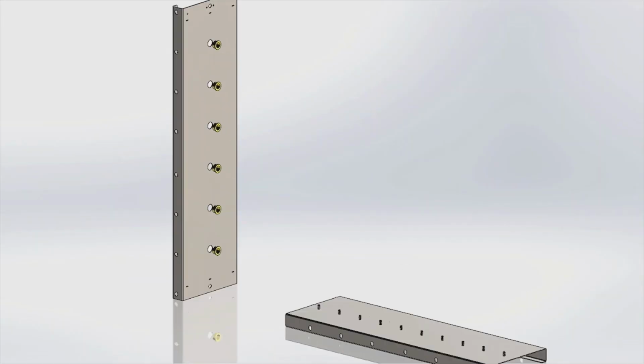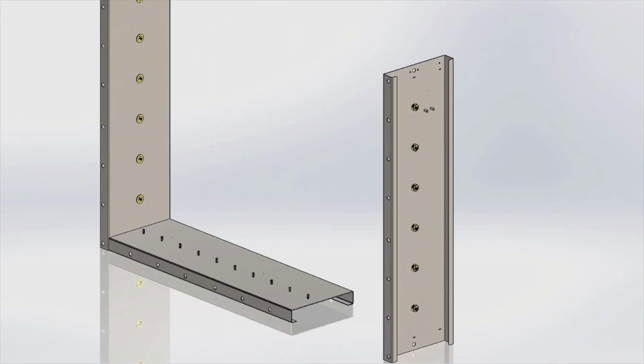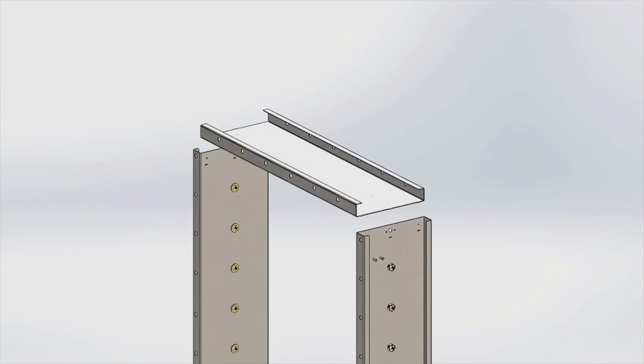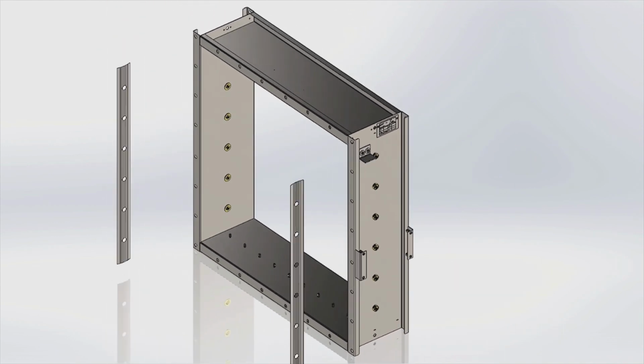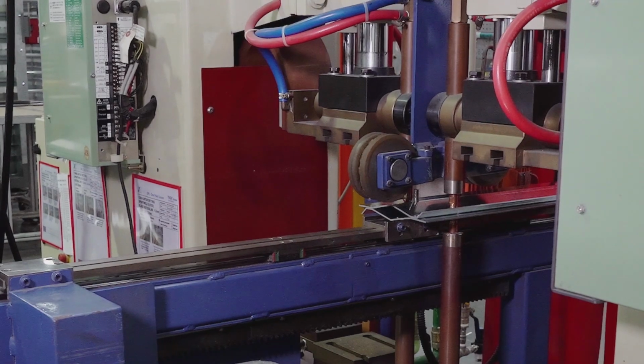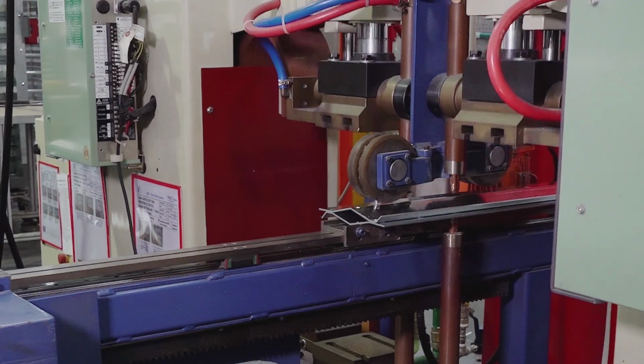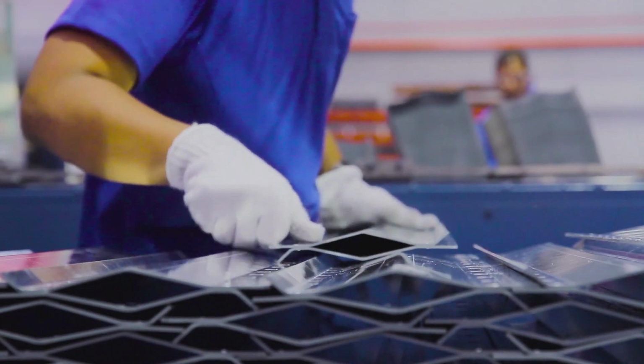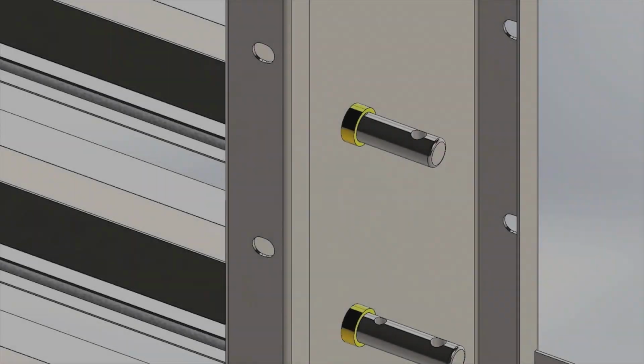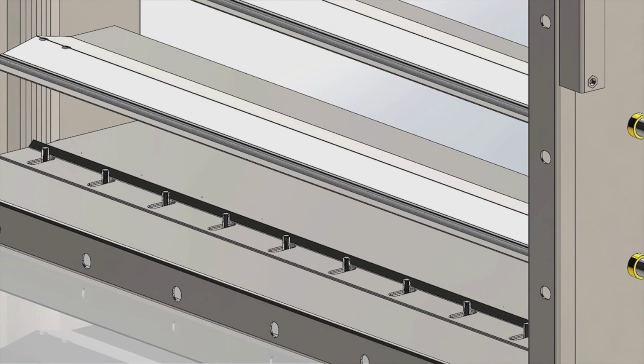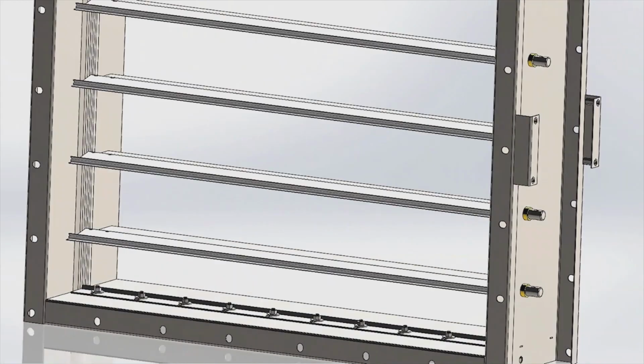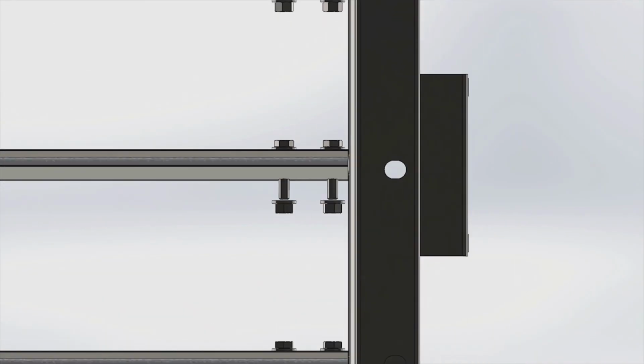The damper case is a rigid, fully welded structure of minimum 2 mm thick and maximum 9 mm thick material. The blades are manufactured from a double skin of minimum 1.2 mm thick and maximum 2 mm thick material. The blade shafts are 20 mm in diameter. The blades are bolted to the shafts for easy maintenance.